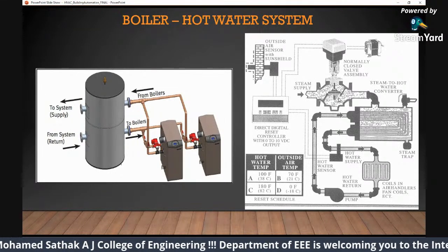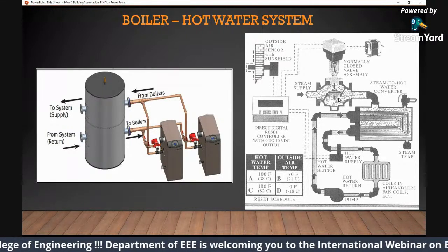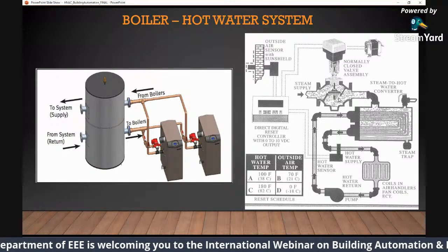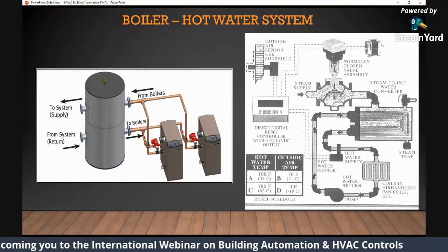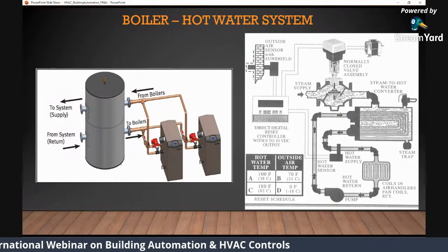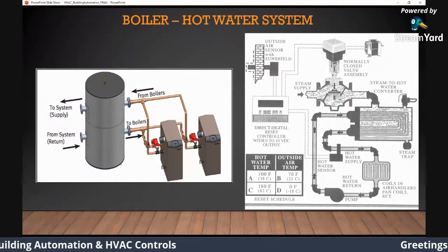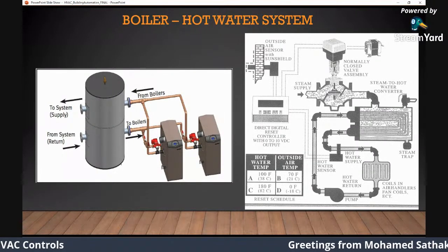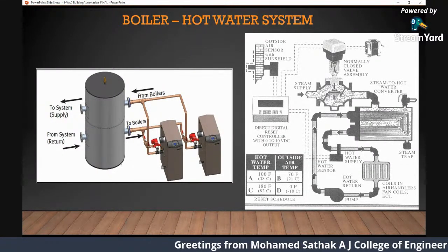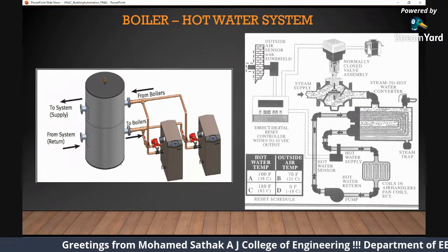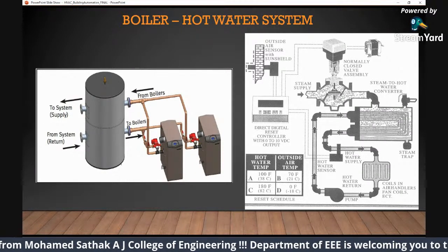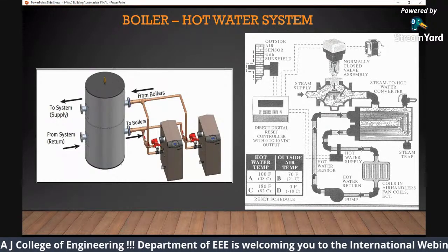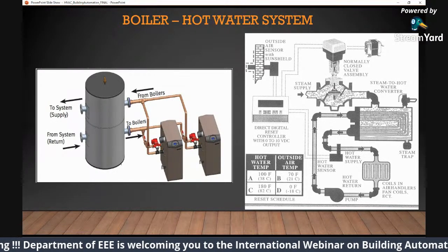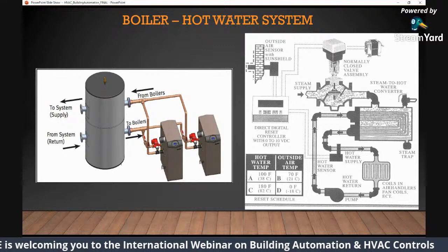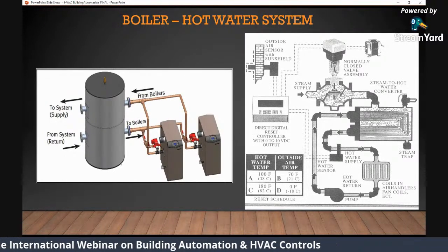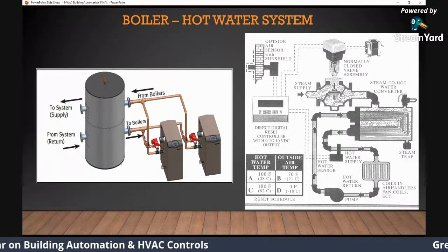Mostly, we determine the hot water temperature based upon the outside air temperature. If it's too cold outside, we increase the hot water temperature. If it's at moderate temperature, we maintain it at 100 to 110. Again, in tropical countries like India or Gulf countries, we predominantly don't use boilers. There is no purpose at all. Sometimes in northern India, Delhi, Jammu, Kashmir, you'll find boilers, but in Western countries, a boiler is a must. Every house will have an HVAC system, and every house will have a boiler. A boiler is a must in all the countries in the West. But in India, air conditioning is a must nowadays. It's getting into every household, but boilers are not suited or not much needed for our country.